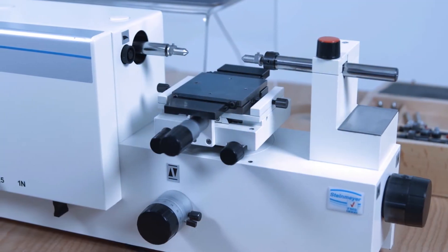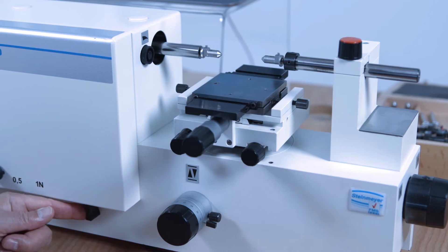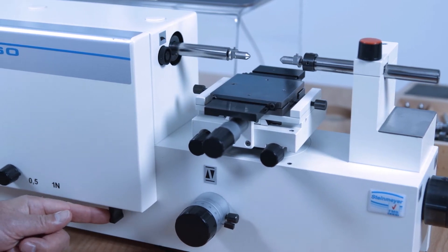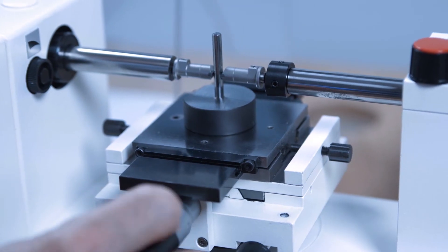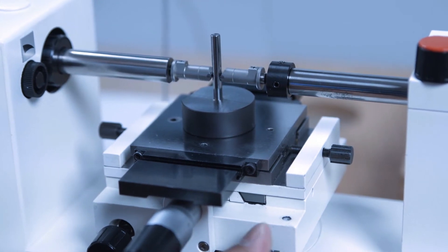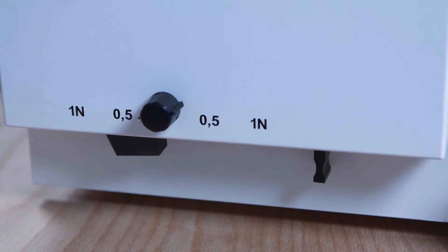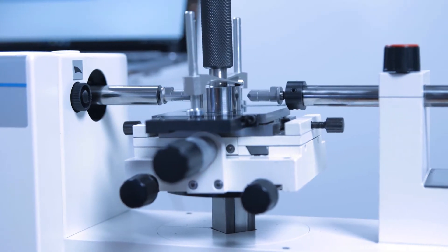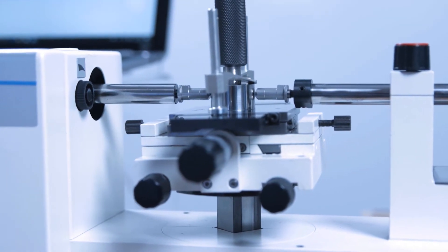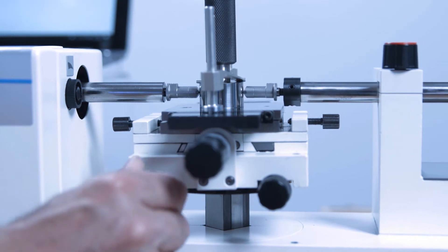The KLM60 measures anything that can be calibrated with a single coordinate length measuring tool in the twinkling of an eye, and does so to the highest precision, strictly following Abbe's principle. Numerous calibration tasks can be performed on specimen sizes up to 120 mm.